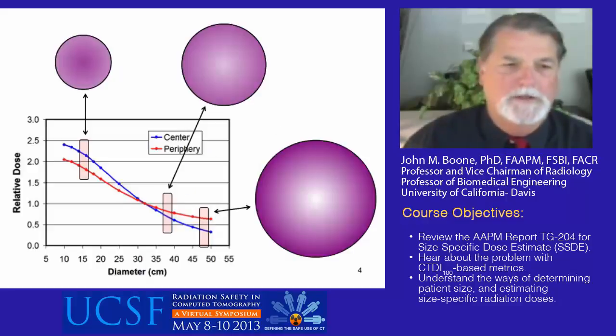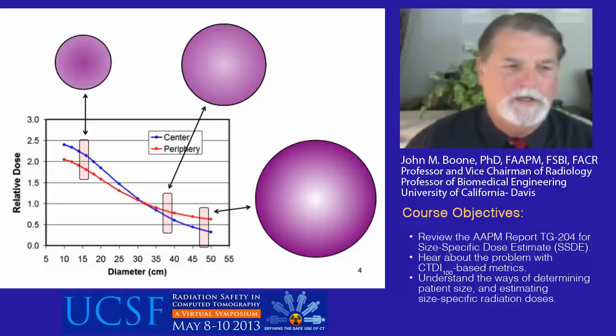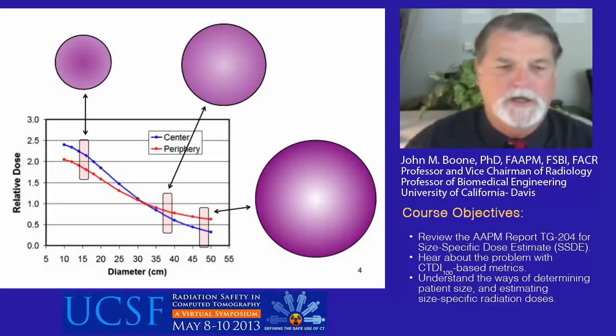One of the limitations of that large 32-centimeter diameter phantom is that it's quite large, much larger than most patients. As shown on slide four, the relative dose as a function of diameter increases for smaller diameter patients, so in general the CT-CTDI value underestimates the dose to a given patient.